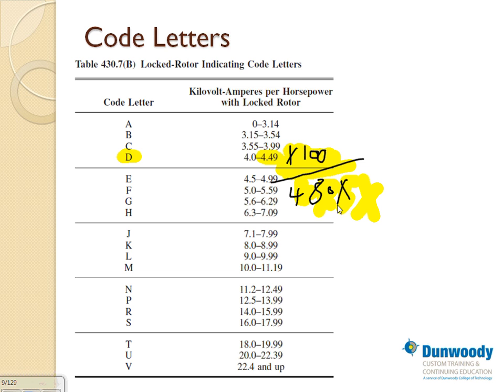There's a multiplier for the 3-phase, so that's always 1.73, and then you multiply everything by 1,000. This is how you find the starting current of a 100 horsepower motor. You take this upper limit number, multiply by all this, divided by the bottom, and that will get you the starting current of this motor. And if you don't believe me, read what they say. These numbers are given in kilovolt-amps per horsepower, so that's why we have to multiply by horsepower. If you were to sit for the exam, get used to this, because that's what you're going to be doing. Any comments, any questions, guys, about this?